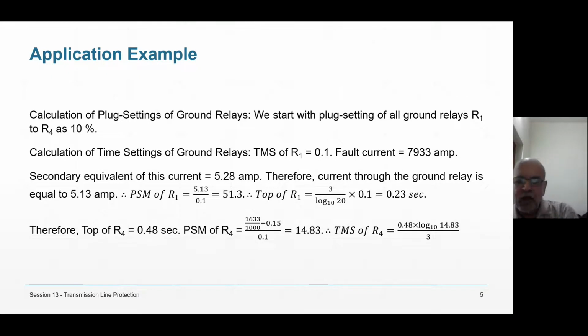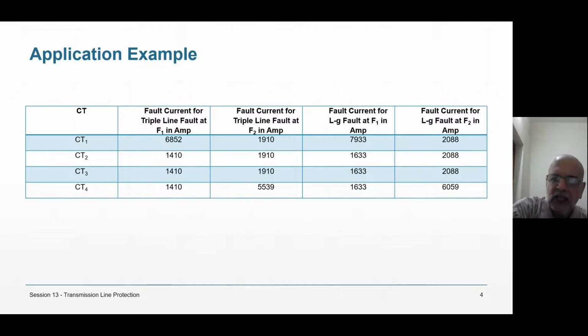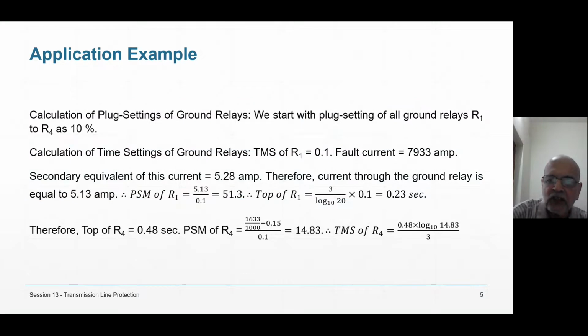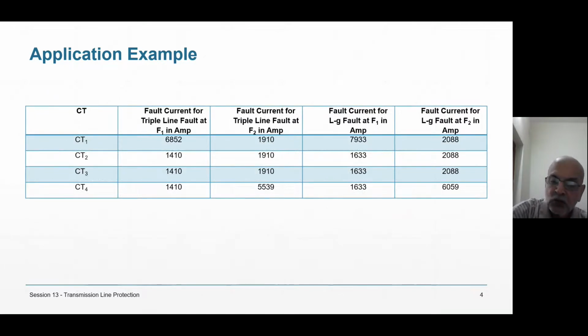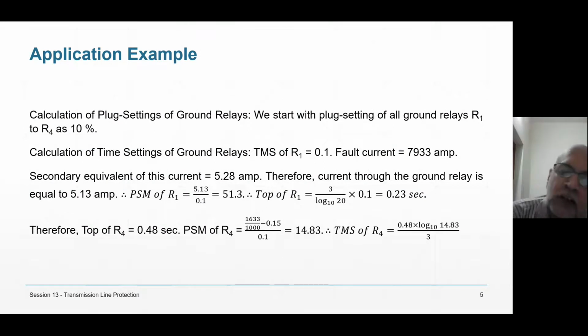So R4, which is going to give backup, its time will be 0.25 second higher. But for that R4, I have to find out PSM. The current flowing is 1633 for the same fault current, for fault F1. So 1633 divided by 1000 minus 0.15, the excitation current, upon 0.1, that is the plug setting, gives 14.83. Yes, I can take that.